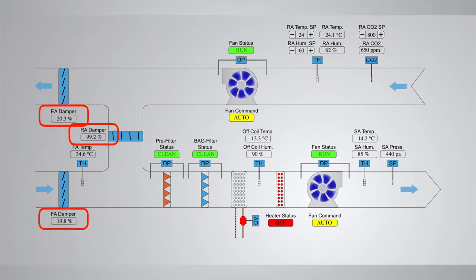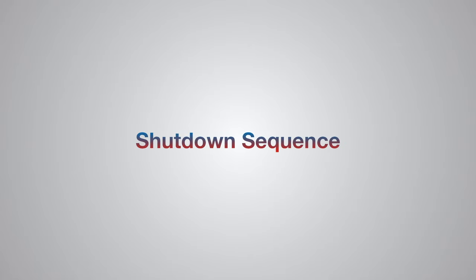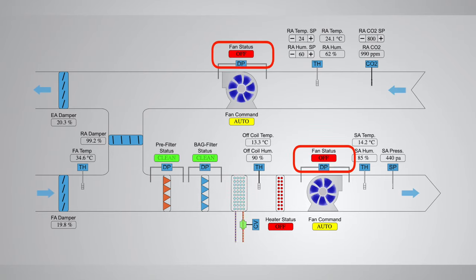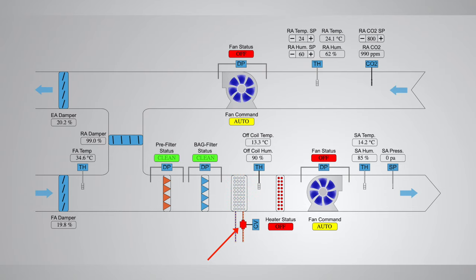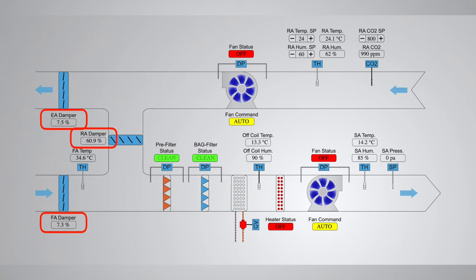The last BMS control is the shutdown sequence. In the shutdown sequence, the fans are switched off first, followed by closing the control valve fully, and then closing all the dampers. All control loops will be disabled until the startup sequence is initiated again.